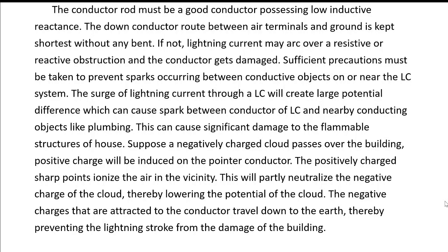Sufficient precautions must be taken to prevent sparks occurring between conductive objects on or near the LC system. The surge of lightning current through a LC will create a large potential difference which can cause a spark between the conductor of LC and nearby conducting objects like plumbing. It can cause significant damage to the flammable structures of the house.